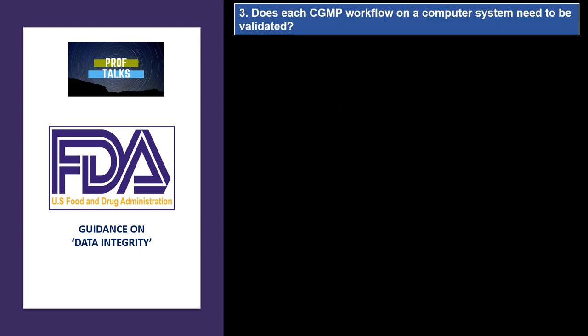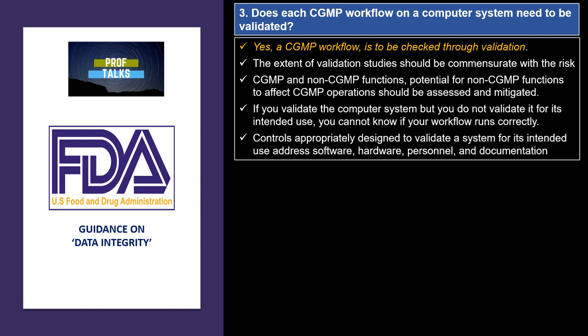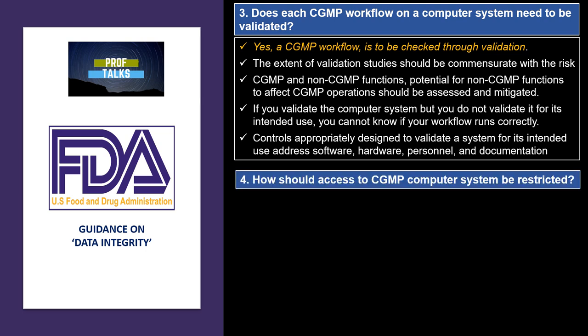The next question is: does each CGMP workflow on a computer system need to be validated? The answer is yes — if the workflow is a CGMP workflow, it needs to be validated. However, the extent of validation is commensurate with the level of risk. There should be consideration of CGMP and non-CGMP functions and the impact of non-CGMP functions on CGMP functions. Validation activities should be carried out for the intended use of the system so the workflow can be run correctly. Controls appropriately designed to validate a system for its intended use address software, hardware, personnel, and documentation.